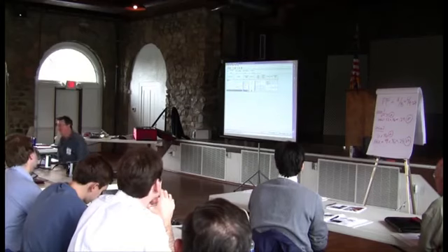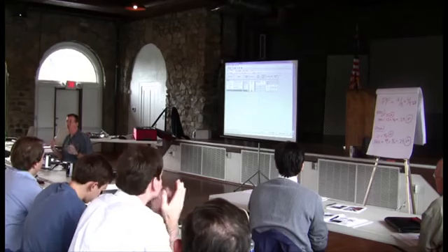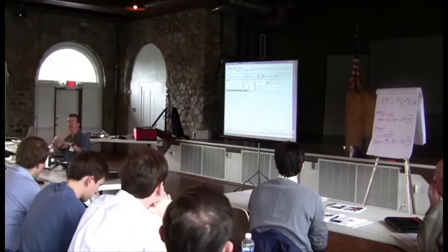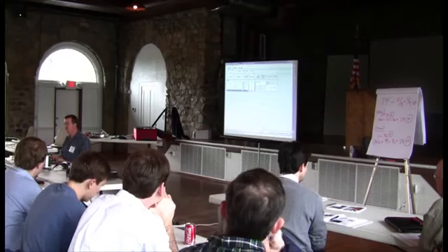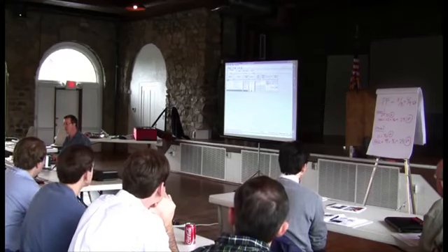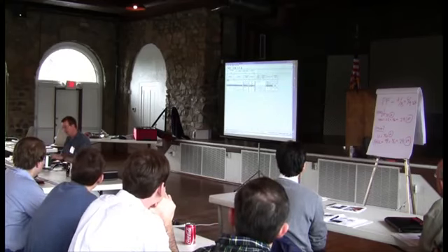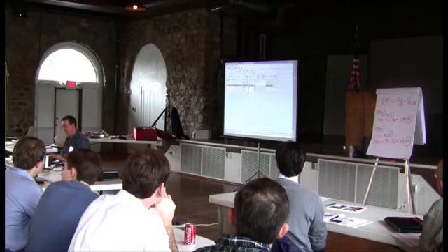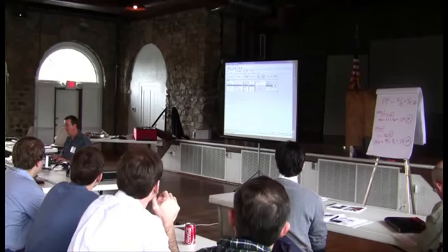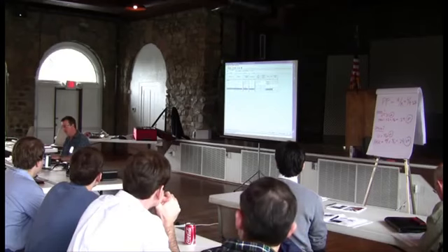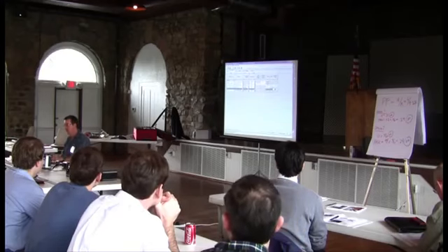Okay, so at the end of the day, it's looking at the whole building, and it's saying, on average, your building right now is 5% worse than code. But when I put a projection factor and shade this glass, 0.67, all of a sudden I'm actually 1% better than code. So the shading has a big swing on this because it's going to affect cooling, and it recognizes that.